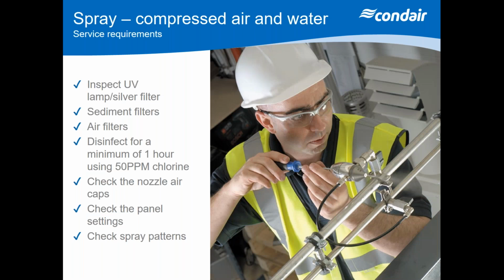So with these, again, you're going to be doing your 2 disinfections a year to 50 ppm. And what we're trying to do is get 50 ppm right to the ends of the lines of these spray nozzles. We have end-of-line valves, which we will normally take a reading from to make sure we're getting 50 ppm at the end of the line. So we know it's coming into contact with all the pipes on the water side to make sure that's being kept clean. And we'll hold that in there for an hour or so, depending on the size of the system, and then we'll drain that away to neutralize it to drain.